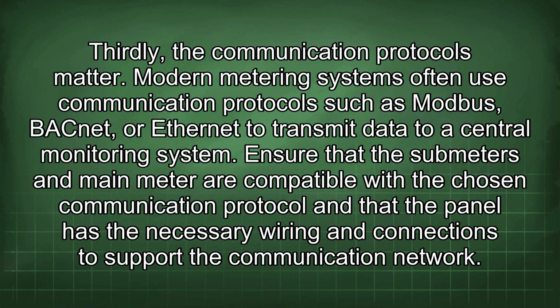Thirdly, the communication protocols matter. Modern metering systems often use communication protocols such as Modbus, BACnet, or Ethernet to transmit data to a central monitoring system. Ensure that the submeters and main meter are compatible with the chosen communication protocol and that the panel has the necessary wiring and connections to support the communication network.